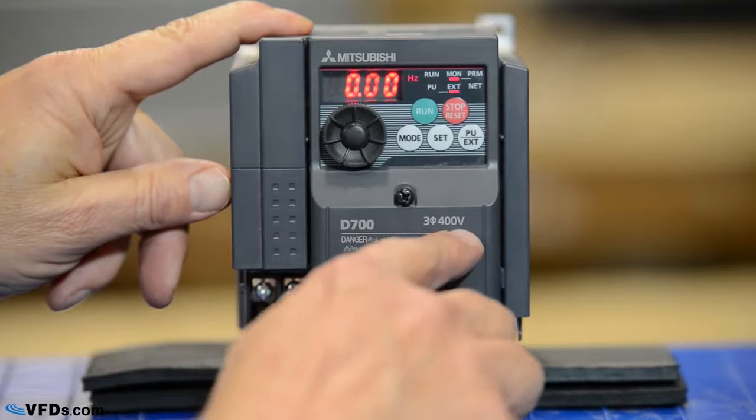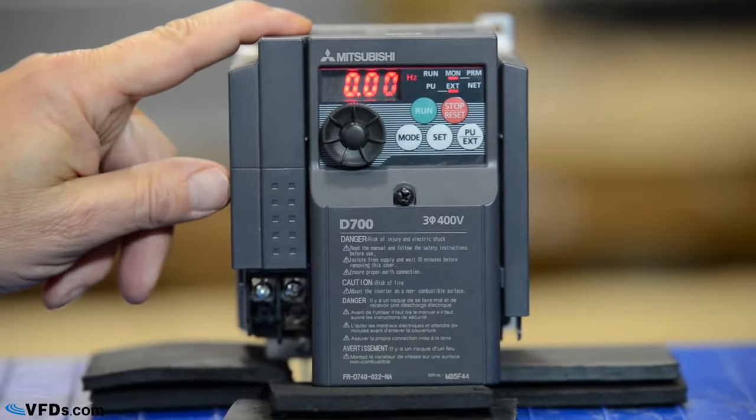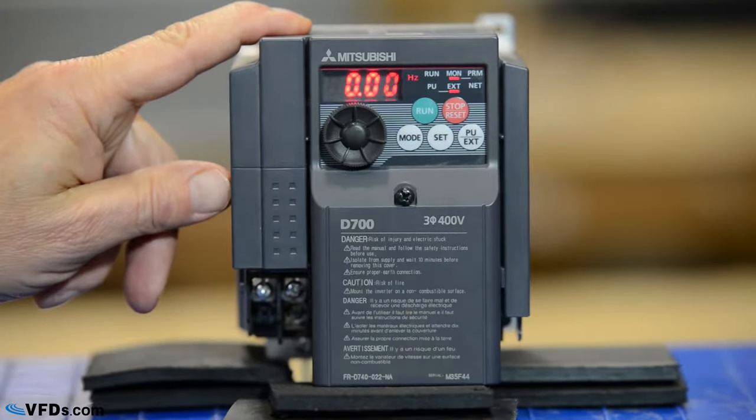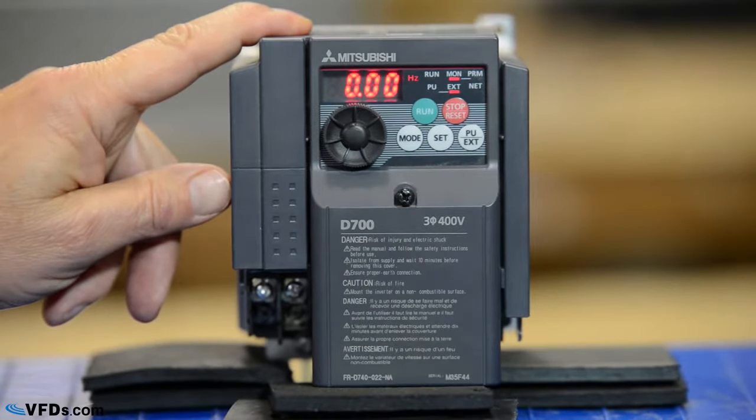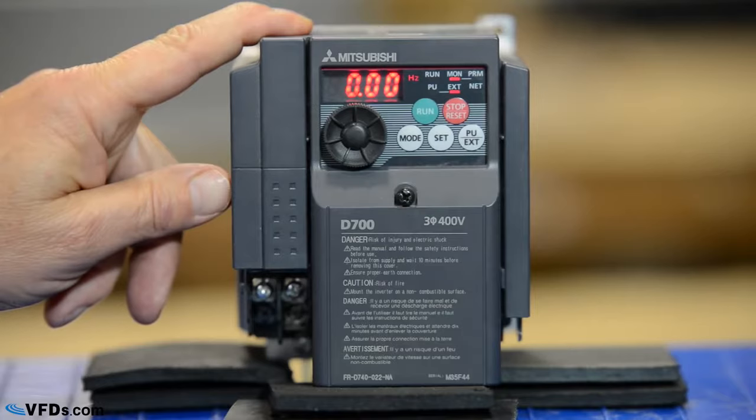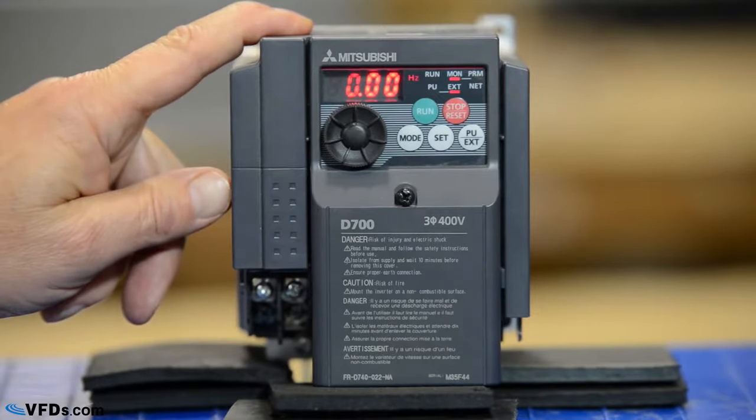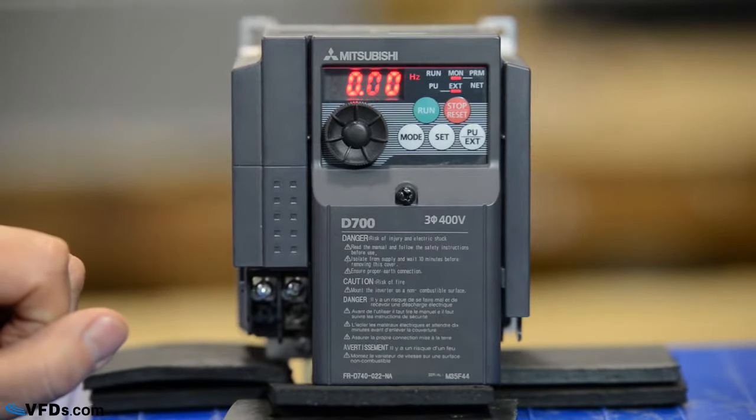This is a 400 volt drive, so we're powering it right now with 480 volts three-phase. It's a 2.2 amp drive, suitable for a one or one and a half horsepower 480 volt motor. We're going to be using the standard programmer that comes with the drive today.